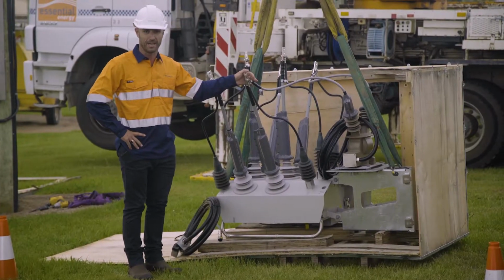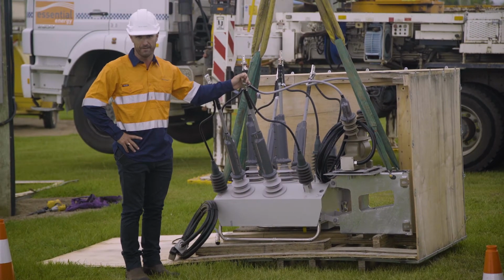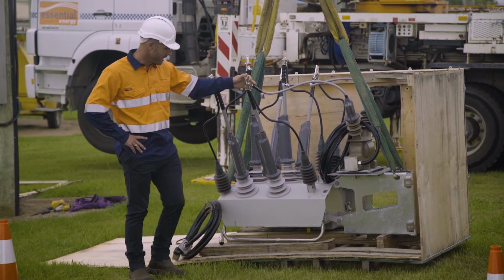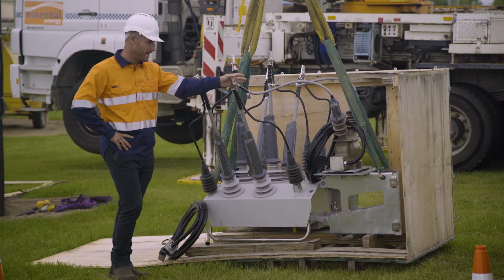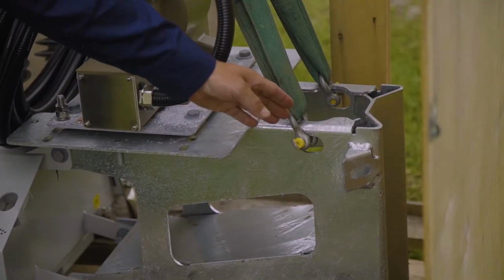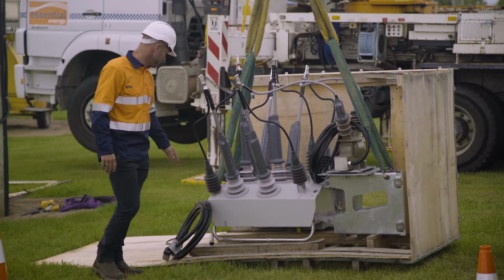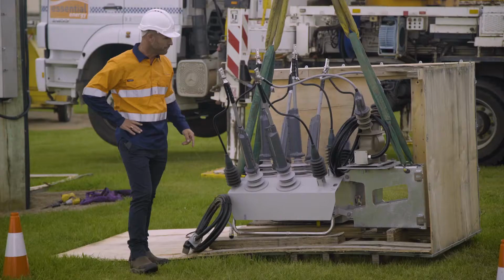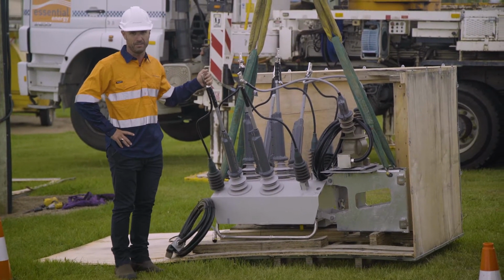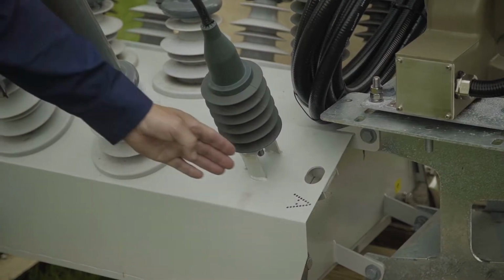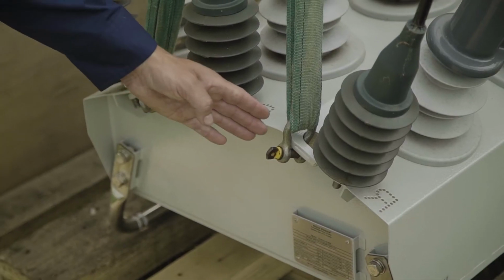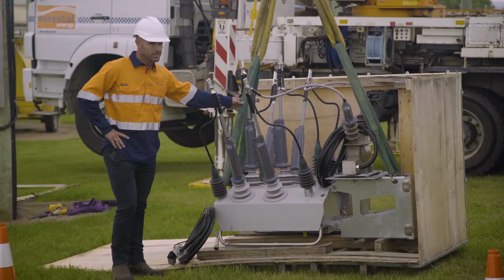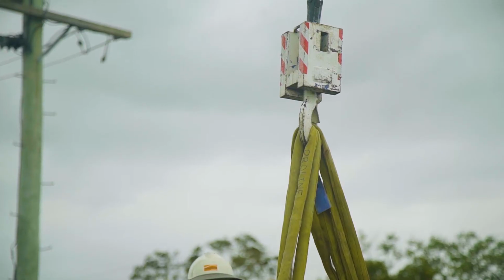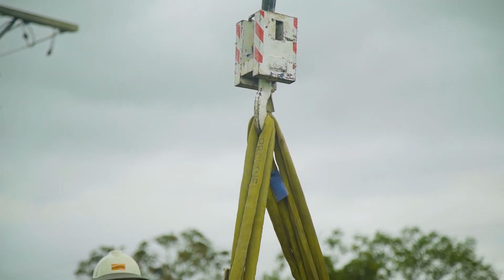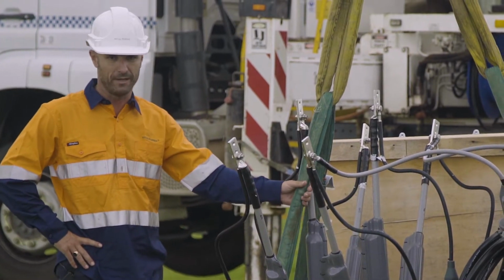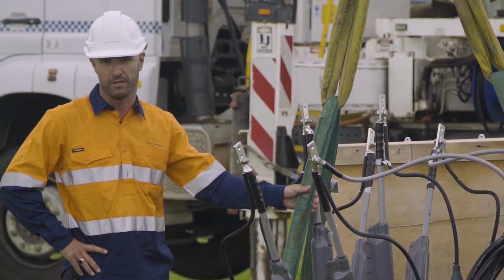For this particular installation, Essential Energy are using a combined VT mounting bracket, and when we're using this type of installation, we have lifting points on the VT bracket and lifting points on the end of the switch. If we were using the VT bracket that sat on the opposite side of the pole, we would use the lifting points on both sides of the switch. We've also now attached the sling and we're ready for lifting. It's important to check that the sling is clear of the bushings so that when we lift the switch, we're not applying any pressure to the bushing.